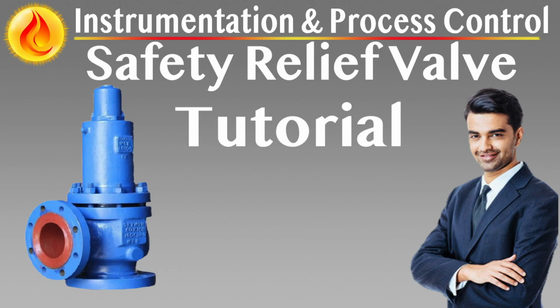HAZOP thermal expansion relief valves, TERVs, localized overpressure protection for blocked-in liquid systems. Thermal expansion relief valves are specialized pressure protection devices designed to relieve overpressure caused by thermal expansion of liquids trapped in isolated piping segments. Even modest temperature increases can generate substantial pressure in incompressible fluids, leading to potential rupture or joint failure. TERVs provide a compact, automatic, and maintenance-free solution to this risk by safely discharging small volumes of liquid when pressure exceeds the safe limit.